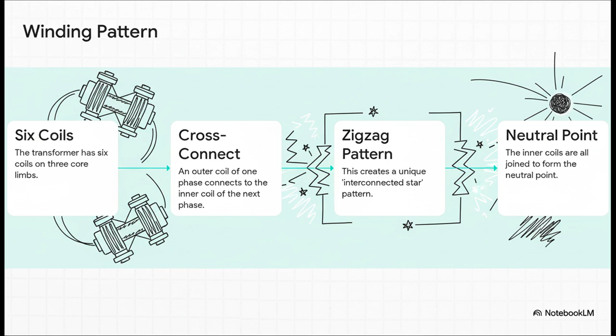When the grid is humming along just fine, the magnetic forces inside are perfectly balanced, they just cancel each other out. It's like two people pushing on a revolving door from opposite sides with the exact same force. Nothing moves. The transformer just sits there, completely idle, drawing almost no power. It's basically invisible to the system.